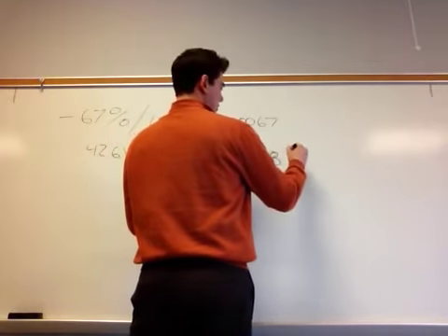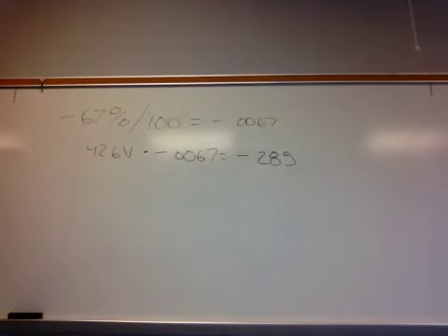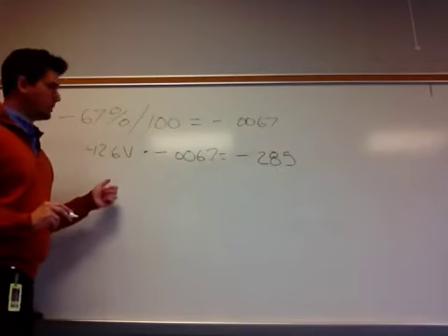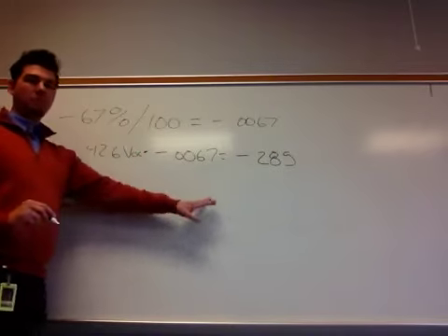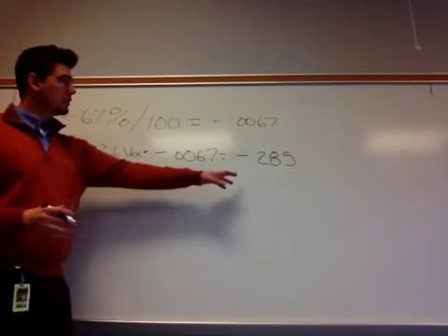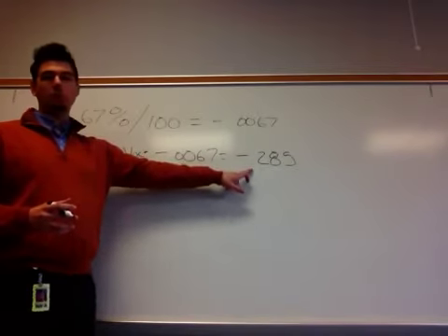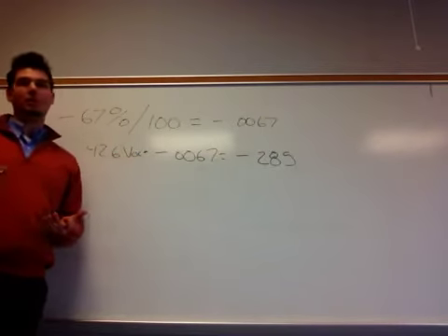Okay, let's go out to the third decimal, shall we? Negative 0.285. So what this tells me is on each module, since they're producing 42.6 VOC, every time the temperature changes, or goes up in this case, the voltage is going to change by 0.285. I know that doesn't seem like a lot, but it depends on how many degrees, right?